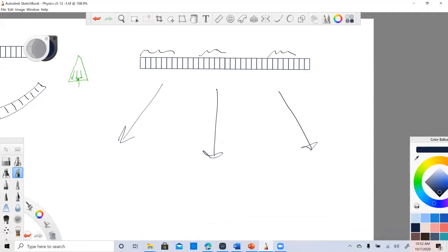Linear phased: every element, every time, pointy top. Linear sequenced: groups of elements. Electronic focusing, steering, flat top. Vector arrays are always steered, like right and left. But unlike the phased array, which kind of sounds like the same thing, the vector arrays are in groups.